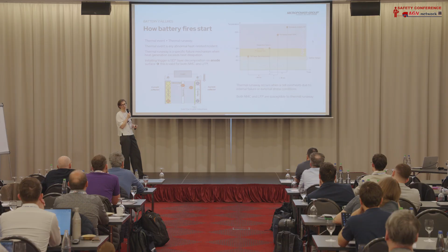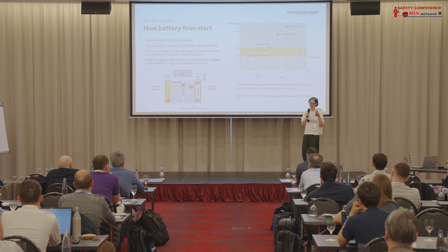the middle, which prevents internal short circuit. When we talk LFP and NMC, we are talking about the cathode material, the positive electrode. But the starting point of a thermal event is actually a failure in the composition of the so-called SEI layer. That layer is located on the anode surface, connected to the graphite. So it's an anode property, not an LFP or NMC property. This needs to be clear.